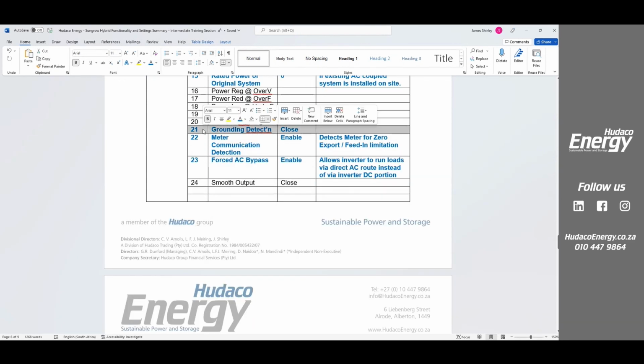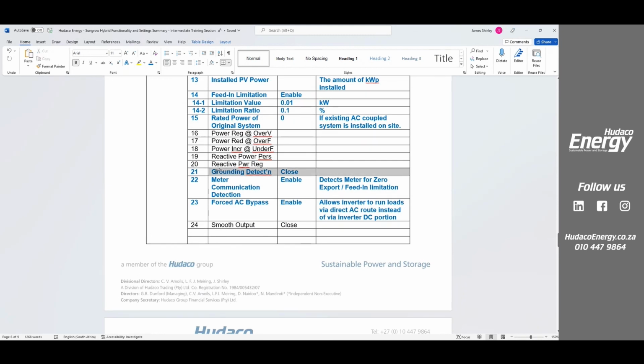Grounding detection, please close this. For South Africa, we are very strict and also very good on the amount of earth leakage devices that get put into houses. The unit itself has the ability to test for earth leakage, which we call grounding detection. The problem is sometimes it'll pick it up and it'll clash with the earth leakage we've got. So make sure you close this grounding detection. Otherwise, you might see an error 304 and the batteries won't connect. It'll say, I've got an issue here. The moment you close that, everything's fine, no issues at all.